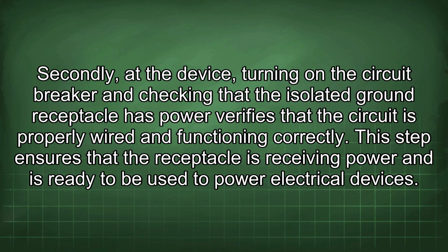Secondly, at the device, turning on the circuit breaker and checking that the isolated ground receptacle has power verifies that the circuit is properly wired and functioning correctly. This step ensures that the receptacle is receiving power and is ready to be used to power electrical devices.